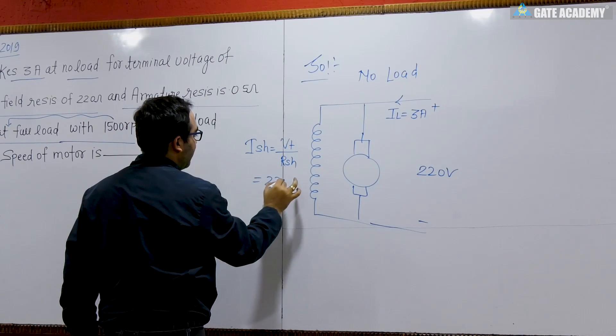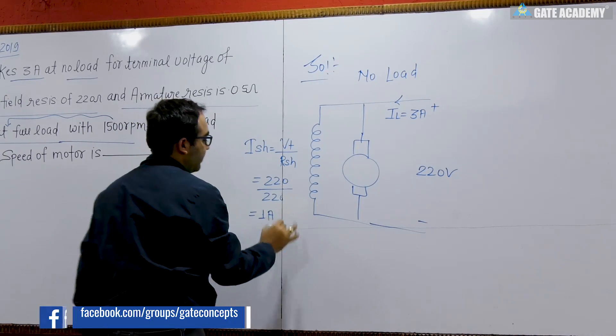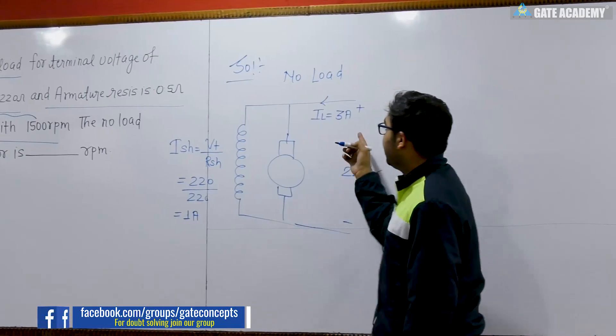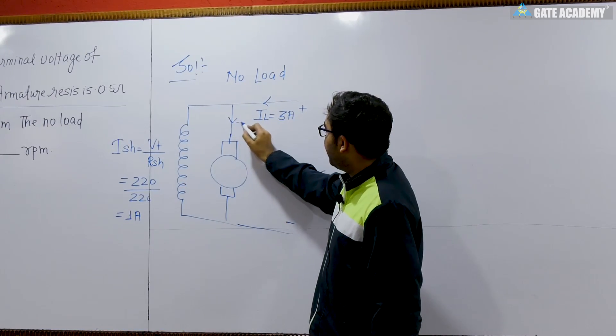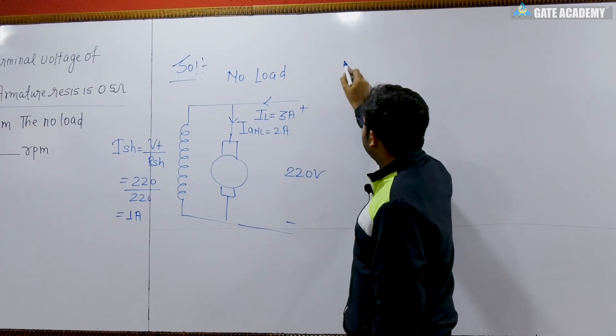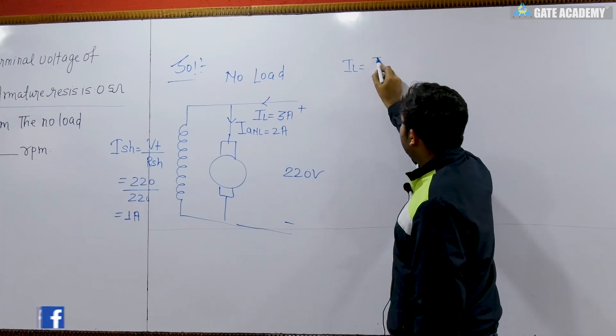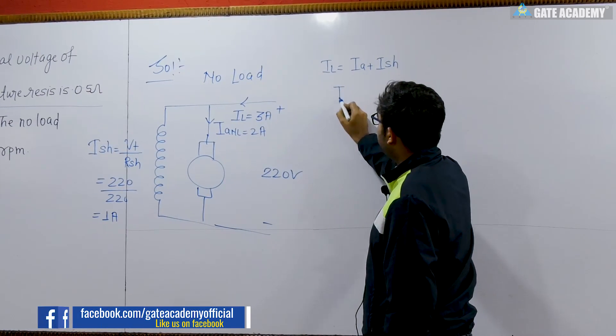So how much? 220 by 220, so this is 1 ampere. Now 3 ampere is taken by the motor, 1 ampere is going in the shunt winding, so it's quite obvious the value of armature current at no load will be equal to 2 ampere. Because for motor, IL equals Ia plus Ish by applying KCL.